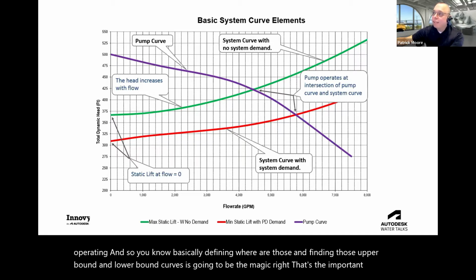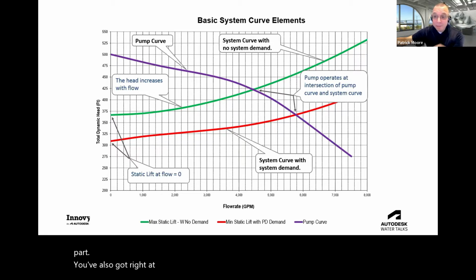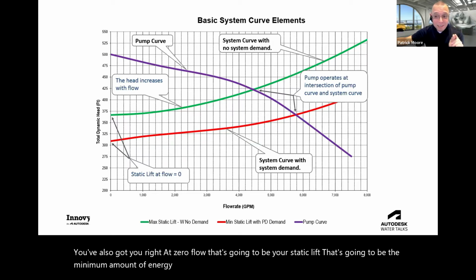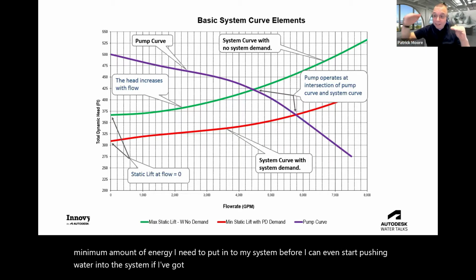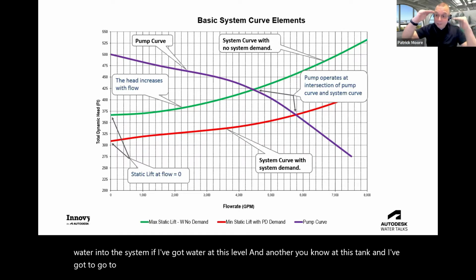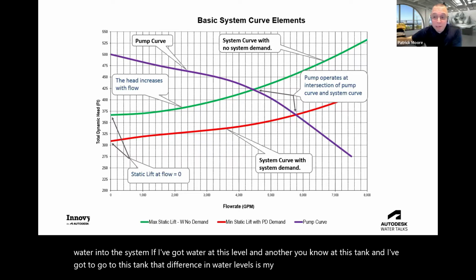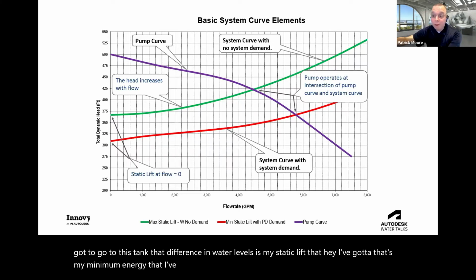You've also got, right at zero flow, that's going to be your static lift. That's going to be the minimum amount of energy I need to put in to my system before I can even start pushing water into the system. If I've got water at this tank, and I've got to go to this tank, that difference in water levels is my static lift, my minimum energy that I've got to put in before I can start pushing water in there.